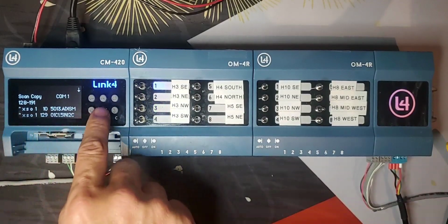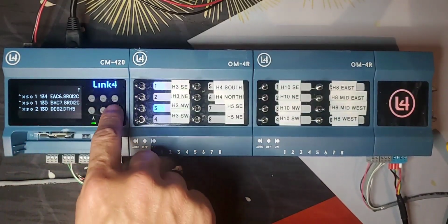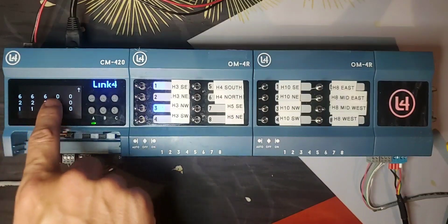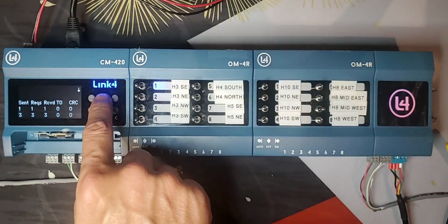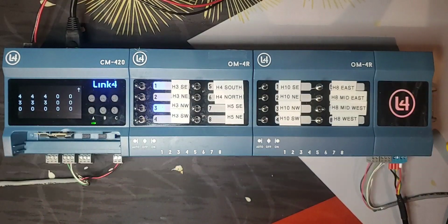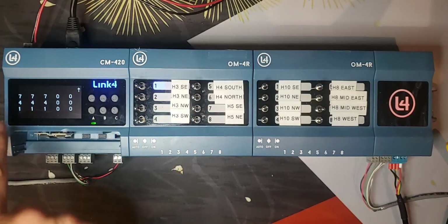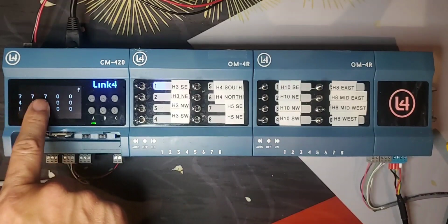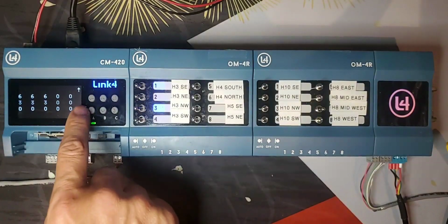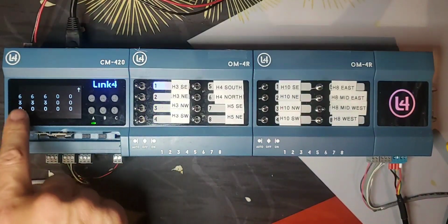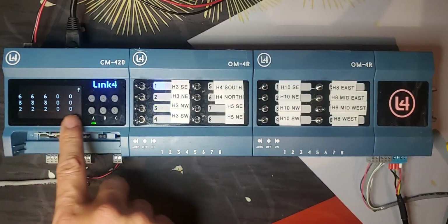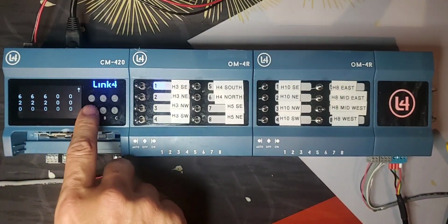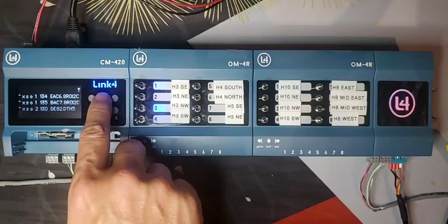Okay, that's these two boards. If I go down, these 3 again, press right. You see 6 coming out, 2, 1. See all the numbers are the same. That's good. Okay. So, 7 requested, 7 was sent, 7 was received. So this is another place for you to look. If you see all 0 here and it never changes, that means there's no communication to that card, to this card here.